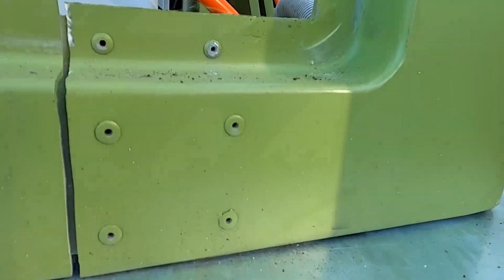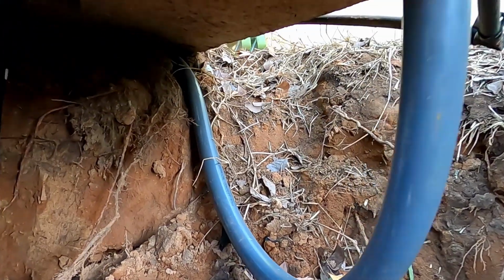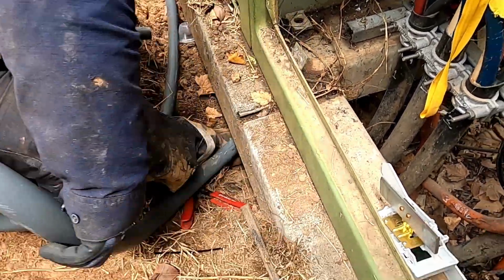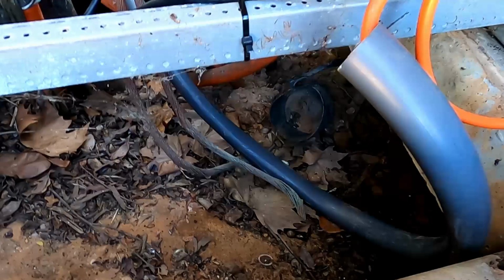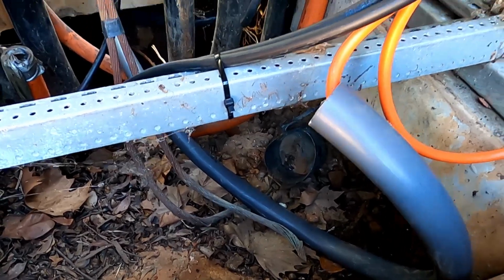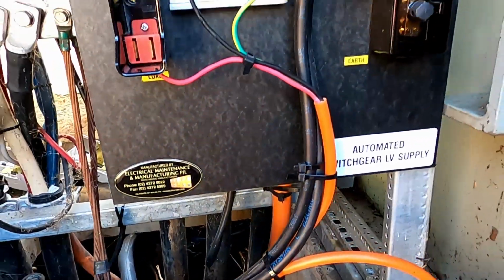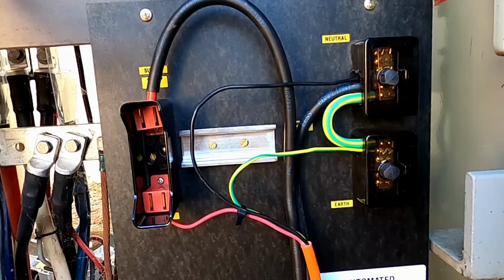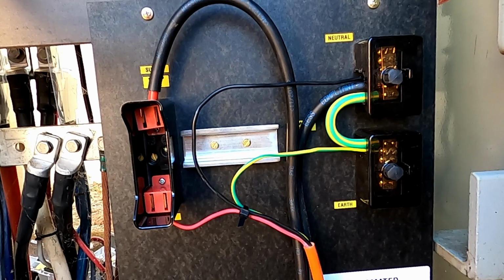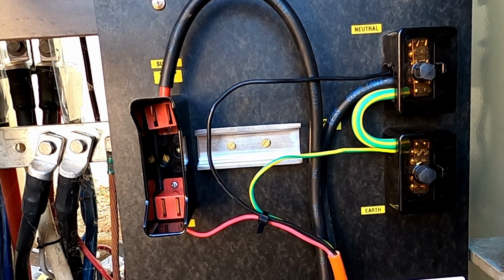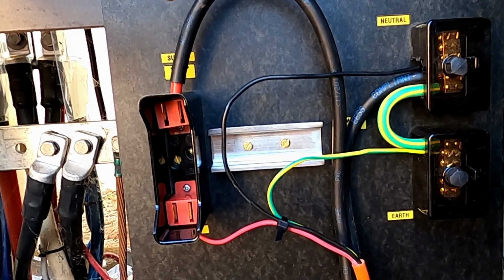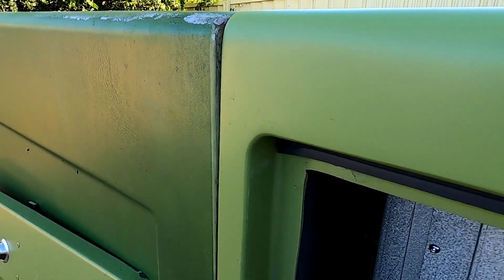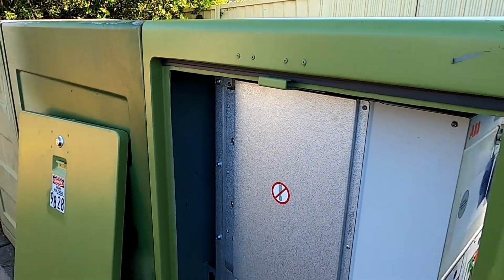Insert the LV supply cabling from the SCADA cubicle into a flexible conduit. Run this conduit under the concrete plinth and feed into the low voltage cubicle. Secure the cable neatly in place and connect the active, neutral and earth to the switchgear low voltage supply. Do not install the fuse. This is done by operators during commissioning. Secure the cubicle doors and complete post-work remediation of the site.